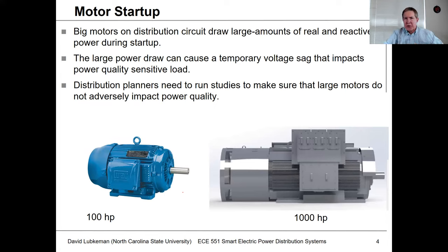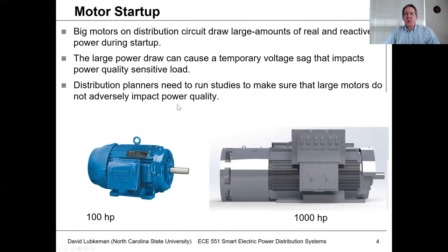When we're talking about motor startup, we're referring to issues associated with large induction motors. Induction motors are the industry workhorse — synchronous machines are more used for generation, but induction motors are more used for loads. The issue is that these machines can draw large amounts of current when they start up, and mostly what they're drawing is reactive current, because when starting up they're not pulling much real current.